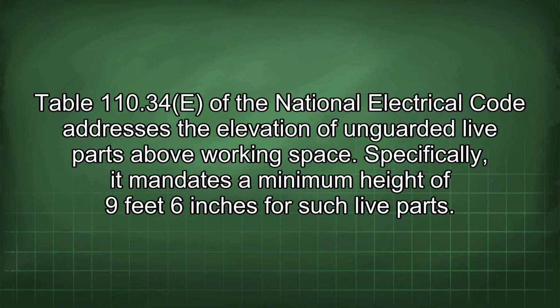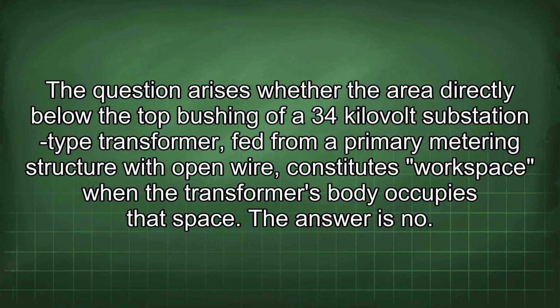Table 110.34(E) of the National Electrical Code addresses the elevation of unguarded live parts above working space. Specifically, it mandates a minimum height of 9 feet 6 inches for such live parts. The question arises whether the area directly below the top bushing of a 34 kV substation type transformer fed from a primary metering structure with open wire constitutes workspace when the transformer's body occupies the space.